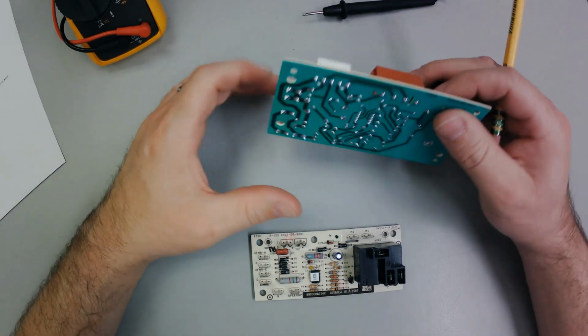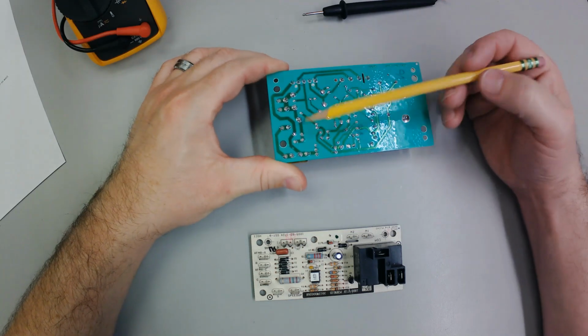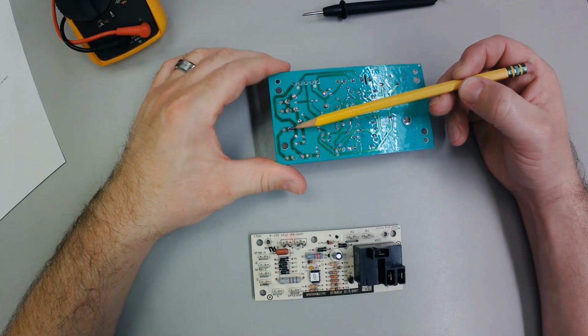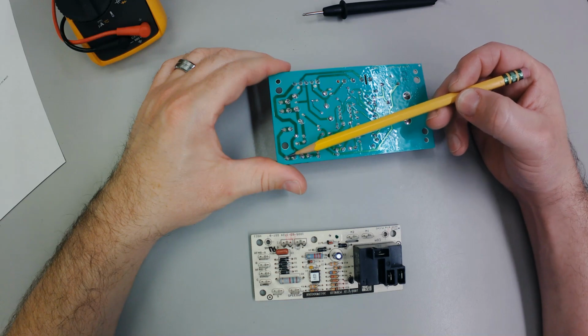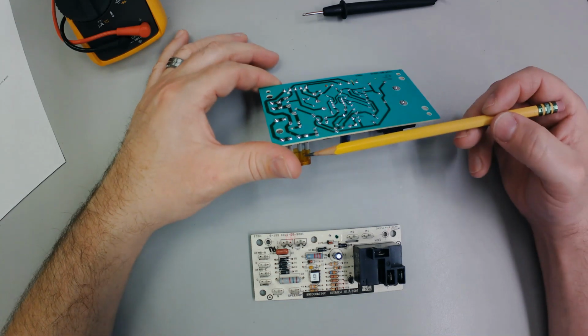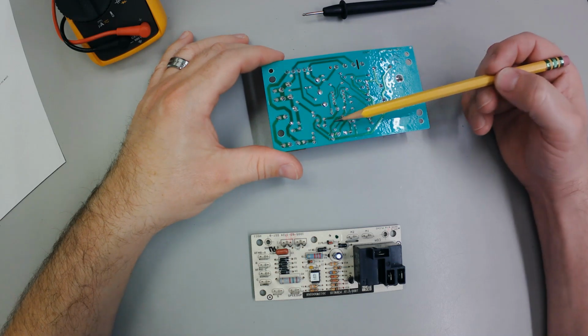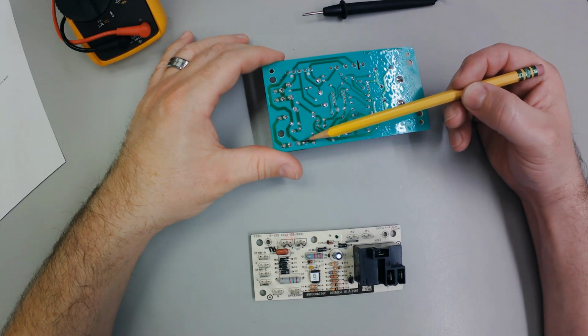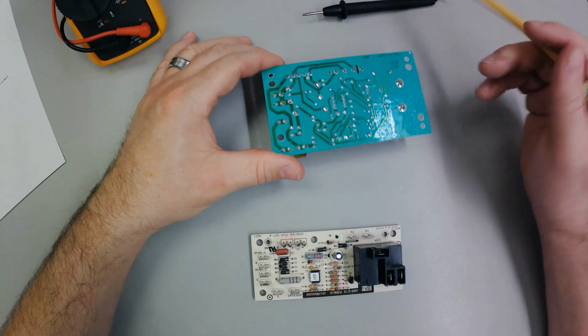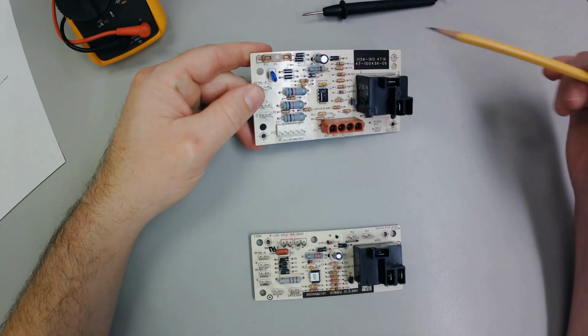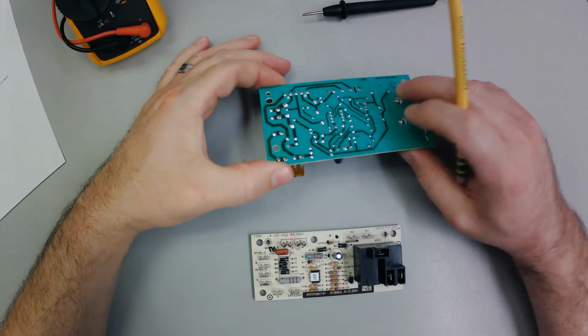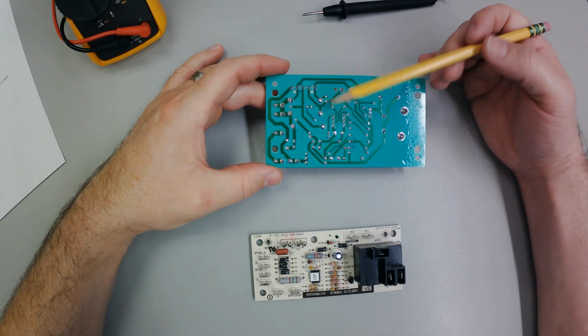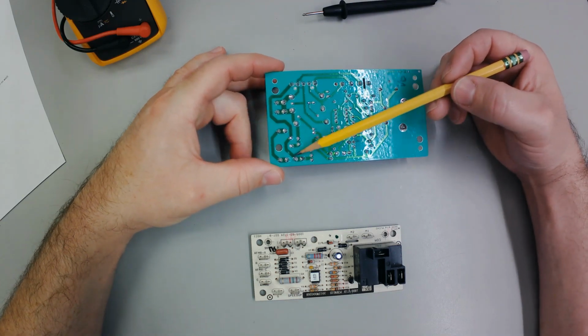All right. If we flip this over, if you were to follow, this is the transformer R. This circuit, you can see it goes into the fuse. If the fuse is good, then it passes power back. When that 24 volts comes back in, it goes through some diodes and stuff to do some work over here. We don't tend to get that deep. We're not electronics gurus, but I have enough sense to follow a line.